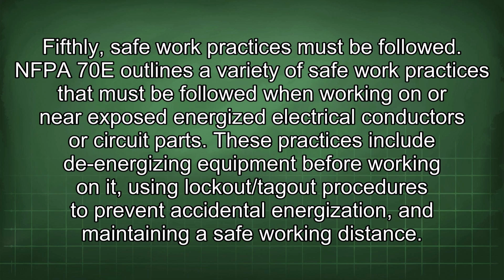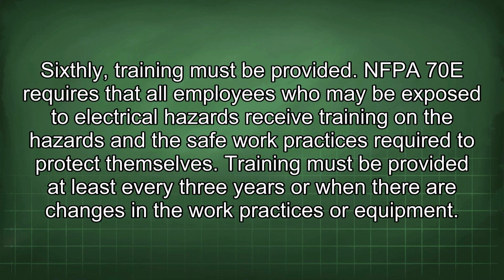Fifthly, safe work practices must be followed. NFPA 70E outlines a variety of safe work practices that must be followed when working on or near exposed energized electrical conductors or circuit parts. These practices include de-energizing equipment before working on it, using lockout/tagout procedures to prevent accidental energization, and maintaining a safe working distance. Sixthly, training must be provided.